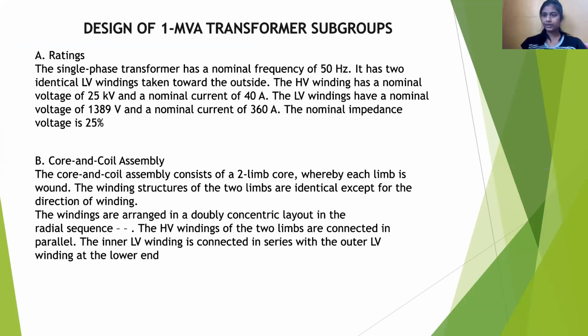Design of the 1 MVA transformer. Ratings. The single-phase transformer has a nominal frequency of 50 Hz. It has two identical LV windings, arranged towards the outside. The HV winding has a nominal voltage of 25 kV and a nominal current of 40 ampere. The LV windings have a nominal voltage of 1389 volts and a nominal current of 360 ampere. The nominal impedance voltage is 25%.